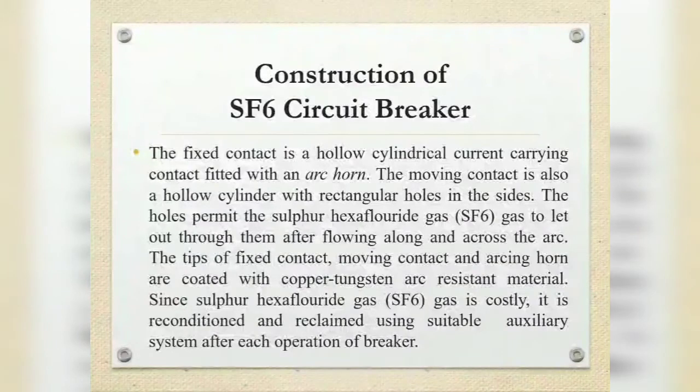The tips of the fixed contact, moving contact and arcing horn are coated with copper tungsten arc resistant material. Since sulfur hexafluoride gas is costly, it is reconditioned and reclaimed using a suitable auxiliary system after each and every operation of the breaker.